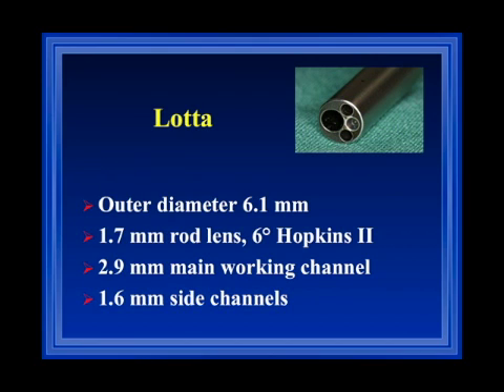The outer diameter of the Lotta ventriculoscope is 6.1 millimeters. It contains a 1.7 millimeter rod lens — a Hopkins II, 6-degree optics — which provides very good image quality, especially when connected to an HD camera. We have a main working channel with a diameter of 2.9 millimeters, and two side channels of 1.6 millimeter diameter, which can be used for irrigation or for the introduction of a second instrument.